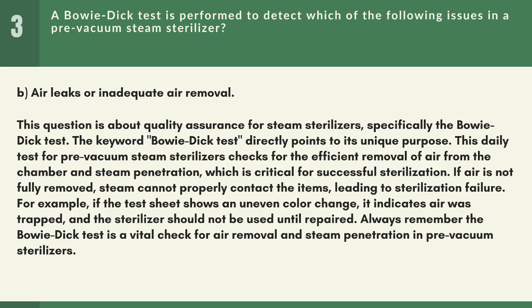This question is about quality assurance for steam sterilizers, specifically the Bowie-Dick test. The keyword Bowie-Dick test directly points to its unique purpose. This daily test for pre-vacuum steam sterilizers checks for the efficient removal of air from the chamber and steam penetration, which is critical for successful sterilization. If air is not fully removed, steam cannot properly contact the items, leading to sterilization failure. For example, if the test sheet shows an uneven color change, it indicates air was trapped, and the sterilizer should not be used until repaired. Always remember the Bowie-Dick test is a vital check for air removal and steam penetration in pre-vacuum sterilizers.